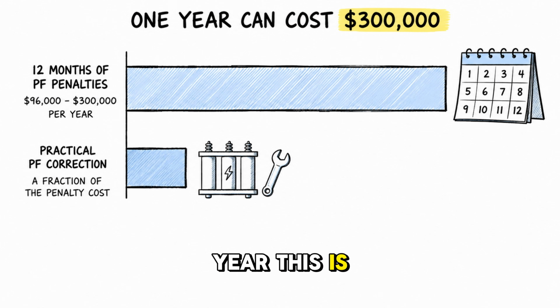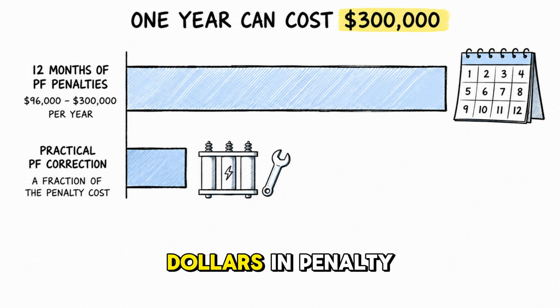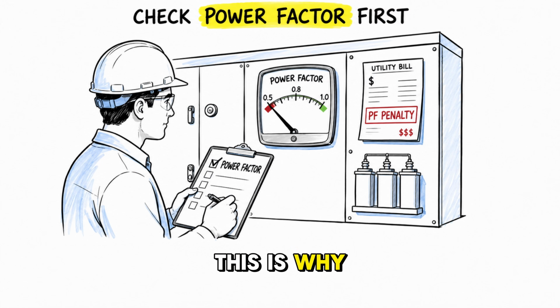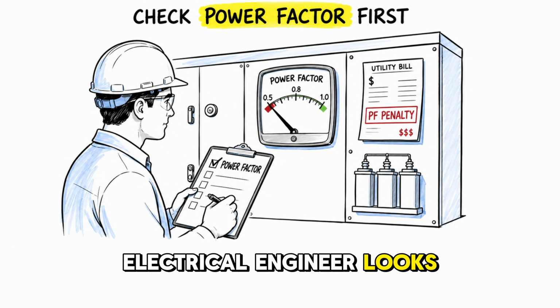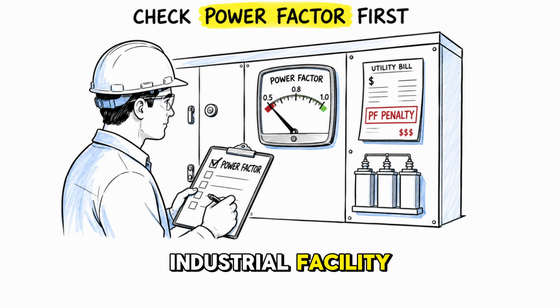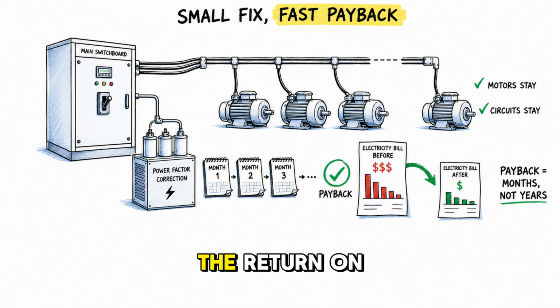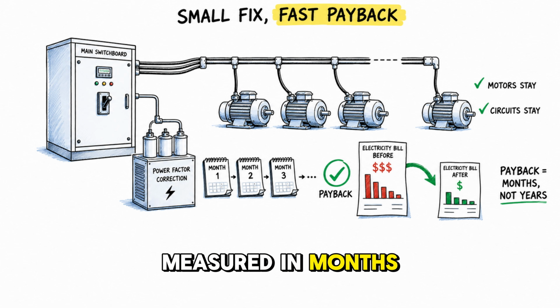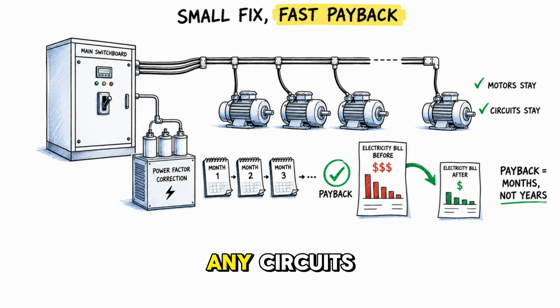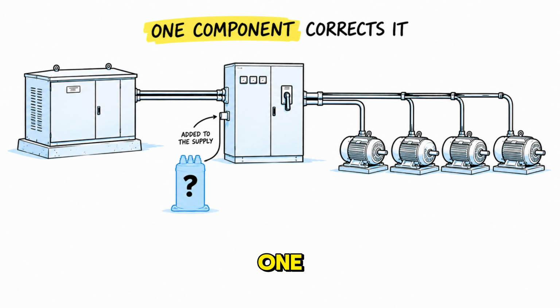Over a full year, this is between $96,000 and $300,000 in penalty charges, for a problem that has a practical engineering solution costing a fraction of that amount. This is why power factor correction is one of the first things a competent electrical engineer looks at when auditing an industrial facility. The return on investment for fixing poor power factor is often measured in months, not years. And the fix does not require replacing any motors or redesigning any circuits. It requires adding one specific type of component to the supply. Let us look at exactly what that is.